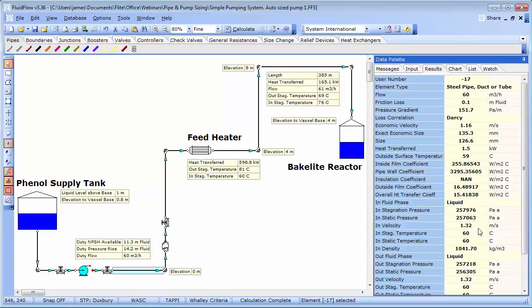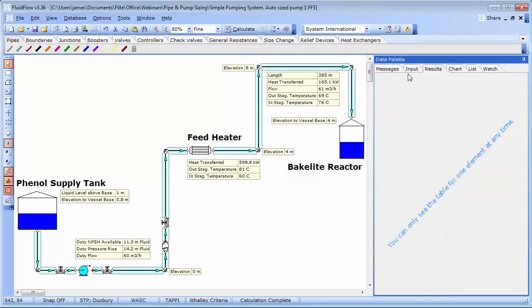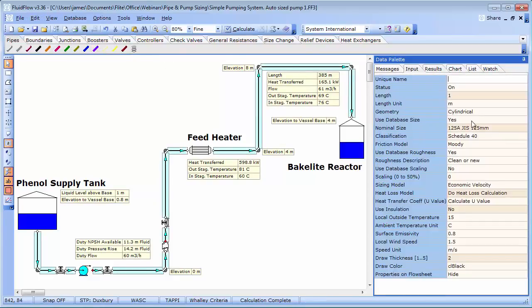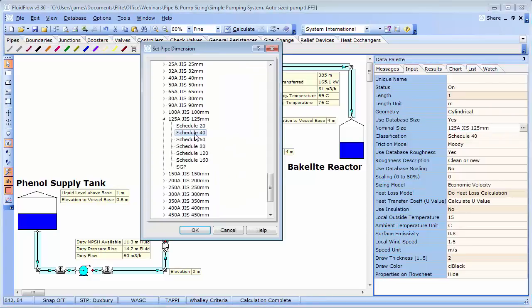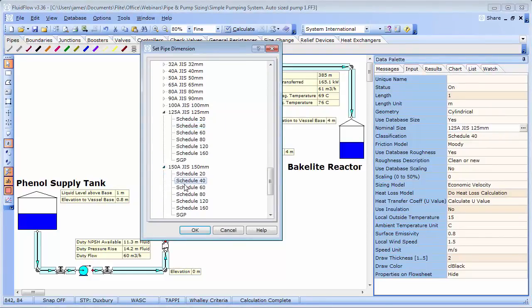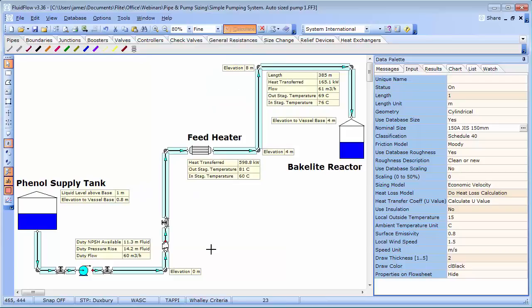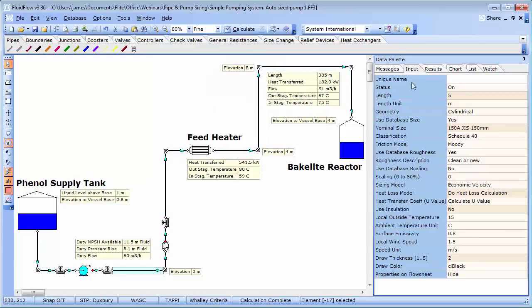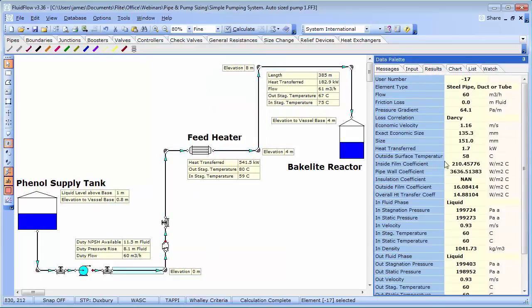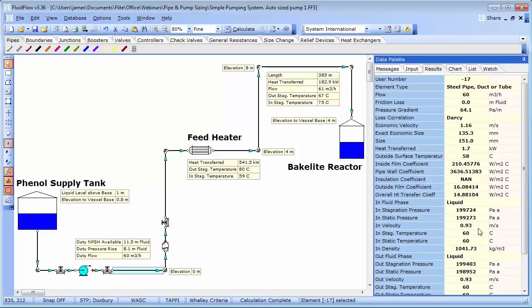We can increase this pipe diameter to 150 and let's have a look at the velocity. Now we can see the velocity is reduced to 0.93 metres per second. The size you choose will depend on your circumstances. Some factors you may wish to consider might be the future likelihood of increasing capacity in the system.